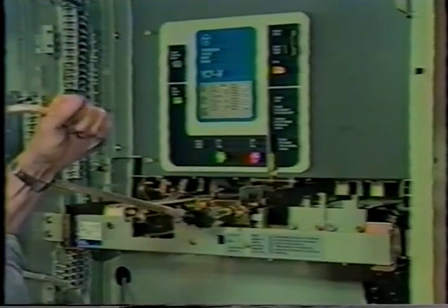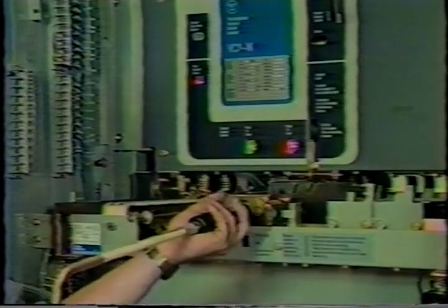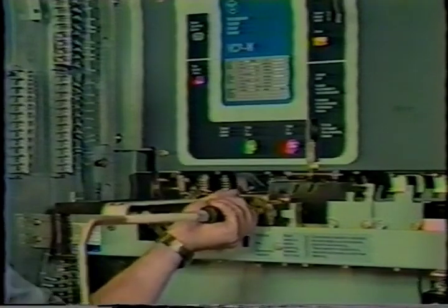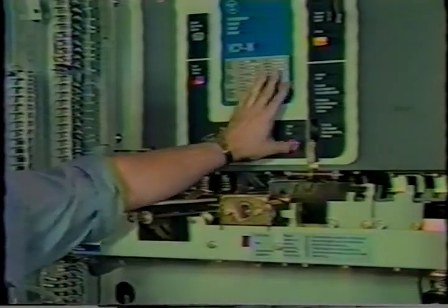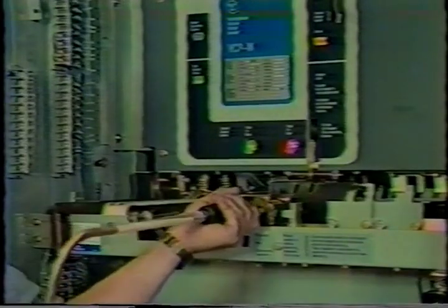Using the levering crank provided, rack the breaker into the connected position. Please note, do not use any tool to lever the breaker from the test to connected position other than the levering crank provided. Correct operation of some of the interlocks is dependent upon use of the levering crank provided with the switchgear. The connected position is indicated by the red flag below the levering nut. Close the circuit breaker. The positive interlock will prevent levering a closed breaker. Now, trip the breaker and withdraw it 6 or 7 turns.